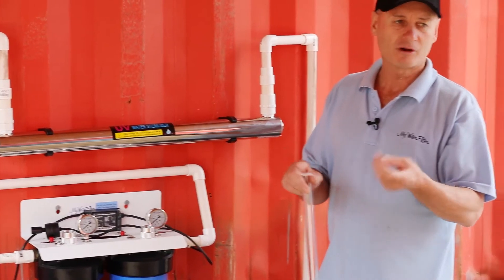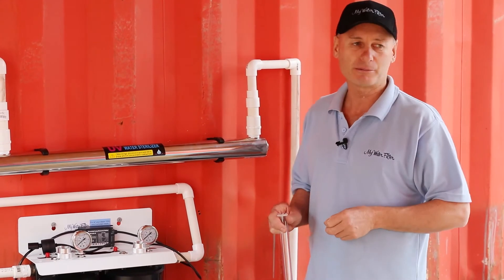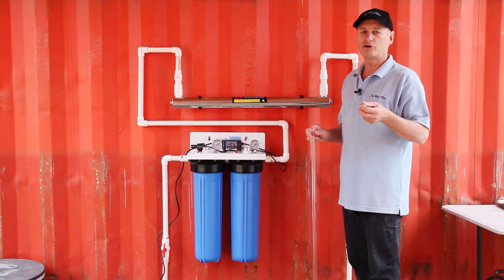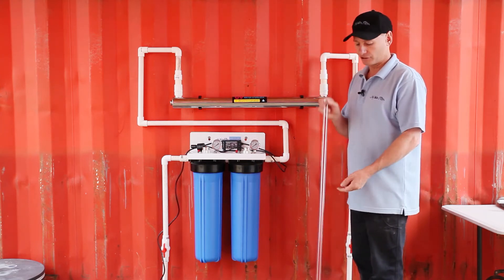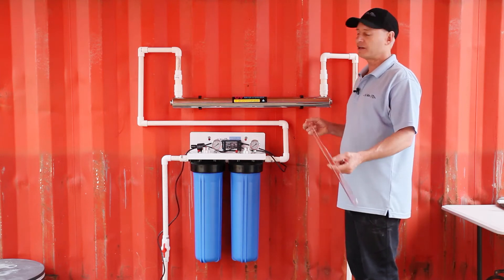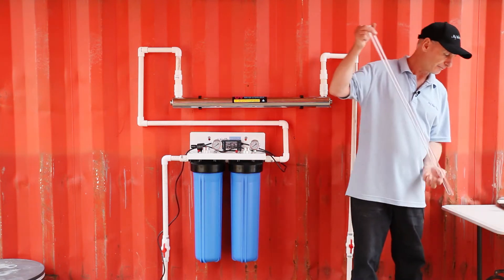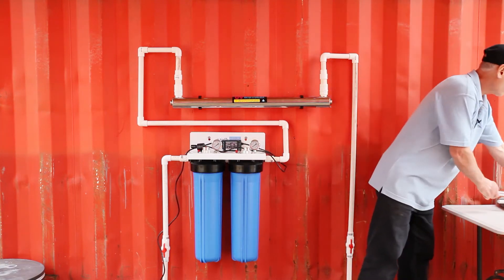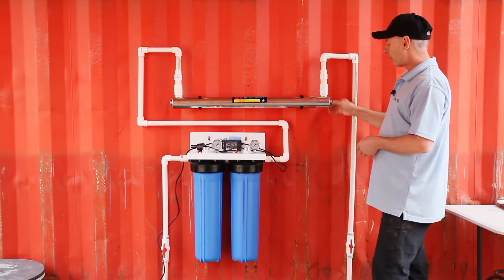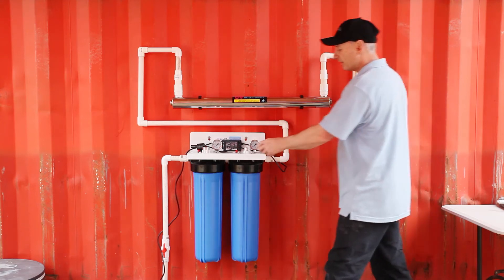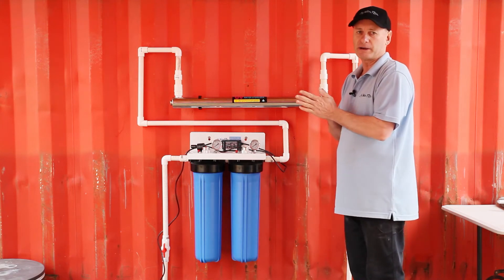For the price of an O-ring, I would change the O-rings every time. I don't want it leaking halfway through the year. I don't want any messing around with it. Short of the power going on and off or a power issue blowing something up, I don't want to be touching this thing. I put it into place, connect it up, and we're done. No need to do anything with it. It should just work perfectly. Keep it dry and you're good to go. Get a cloth, give it a clean up. Make sure our threads are lubricated and the nuts are good to go. Everything's happy and we're happy and it's nice and clean.